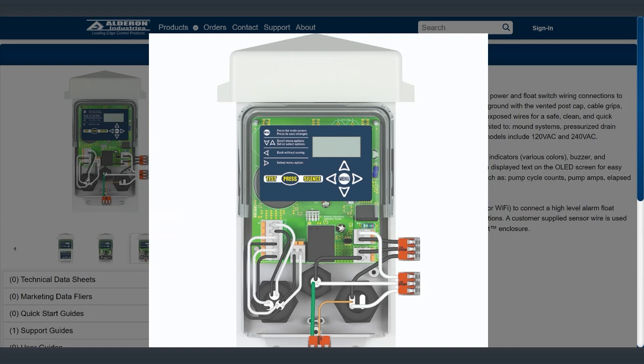So this has separate power inputs. On the bottom right is your pump power, and then on the top right is your alarm power. If they only have one line of power coming in, you can splice it and run it off one. However, if your pump trips a breaker, you're not going to have alarm control, not going to get an alarm indicator. Do you use control floats with that, or you'd have to use a piggyback? You can do either or with the time dose version. So we have it set up, you can do a lot of different things with the time dose version. You can get a low level redundant off alarm.